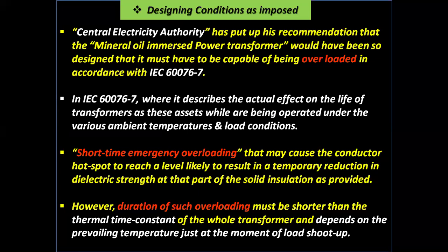IEC 60076-7 describes the actual effect on the life of transformers when these assets are operated under various ambient temperatures and load conditions. Short-time emergency loading may cause the conductor hotspot to reach a level likely to result in a temporary reduction in dielectric strength at that part of the solid insulation. However, the duration of such overloading must be shorter than the thermal time constant of the whole transformer, and depends on the prevailing temperature at the moment the load shoots up.